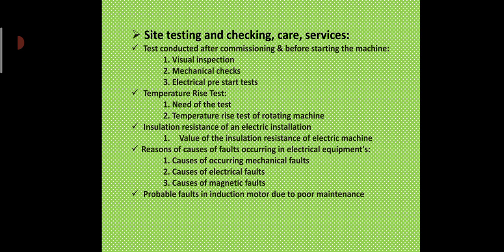Temperature rise test of rotating machines. The motor is loaded directly. The load is of mechanical type, or a DC generator or alternator is coupled to the motor. To the generator, the electrical load is connected. The load is gradually increased until it takes up the full load. Readings for the temperature of the winding are taken periodically. The temperature increases, reaches the final temperature and becomes constant.